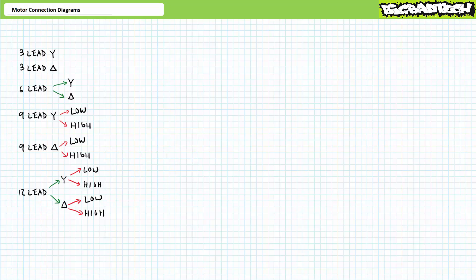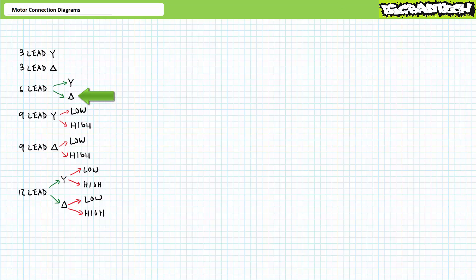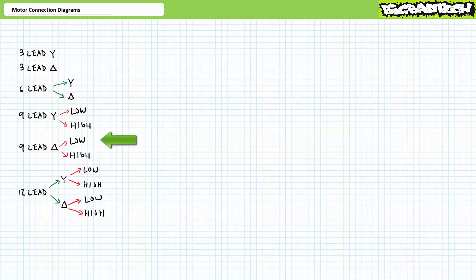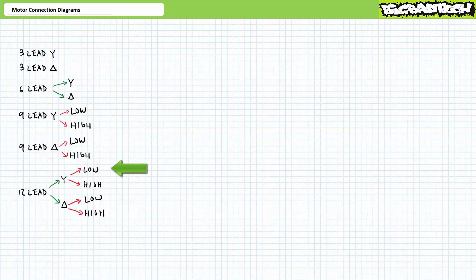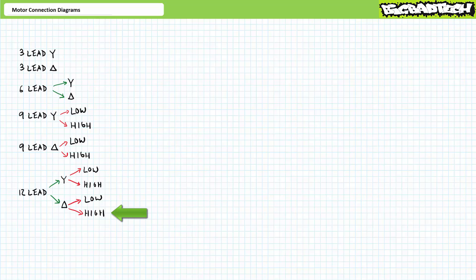This effectively gives us 12 different options: three-lead Y; three-lead delta; six-lead as Y; six-lead as delta; nine-lead Y in low voltage; nine-lead Y in high voltage; nine-lead delta in low voltage; nine-lead delta in high voltage; and finally the most flexible — twelve-lead as low voltage Y, twelve-lead as high voltage Y, twelve-lead as low voltage delta, and twelve-lead as high voltage delta.